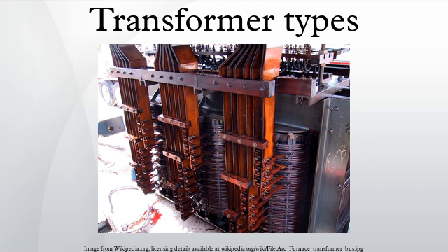Leakage transformers. A leakage transformer, also called a stray field transformer, has a significantly higher leakage inductance than other transformers, sometimes increased by a magnetic bypass or shunt in its core between primary and secondary, which is sometimes adjustable with a set screw. This provides a transformer with an inherent current limitation due to the loose coupling between its primary and the secondary windings. The output and input currents are low enough to prevent thermal overload under all load conditions even if the secondary is shorted.